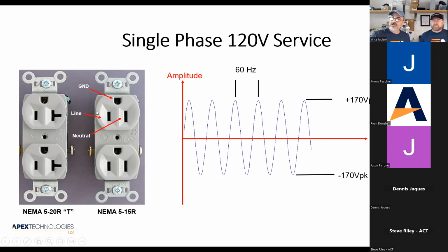Over here, the plug examples that I have on the left side of the page, the ones that we see most commonly for 120 volt service, we have the NEMA 5-15R and the 5-20R. So the 5-15R, as you can see, is the one you see all the time, right? The two vertical blades. The larger of the two blades is the neutral line. If the wiring is connected correctly, and there's no issues with any loads or any wires crossed in the system, the neutral wire should be 0 volts, and that should be safe to touch, as the ground wire is 0 volts. The hot wire is this line, and it's the shorter one.